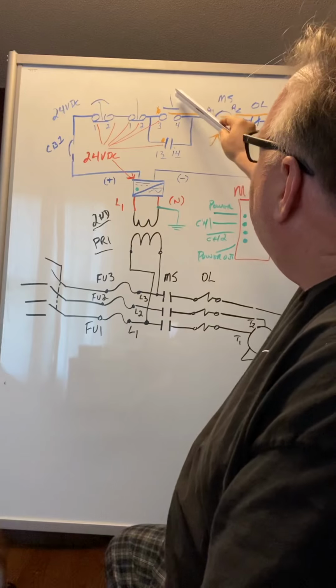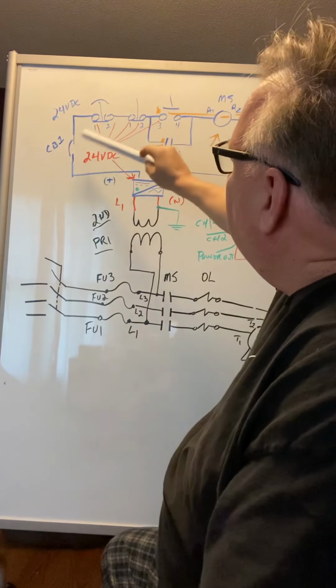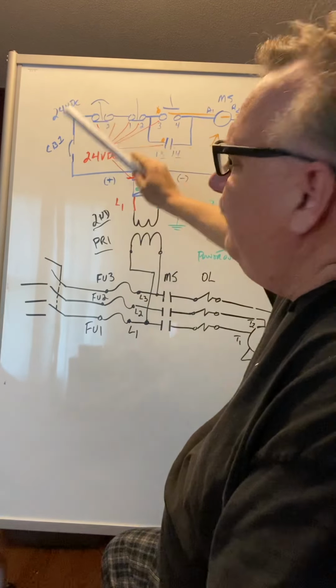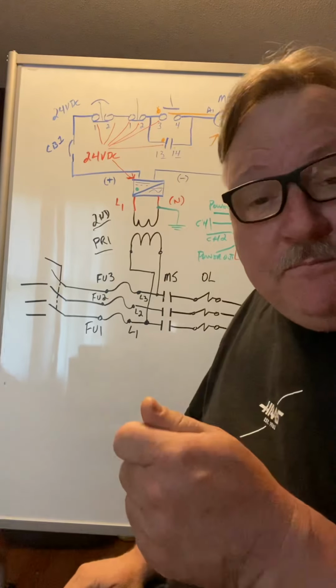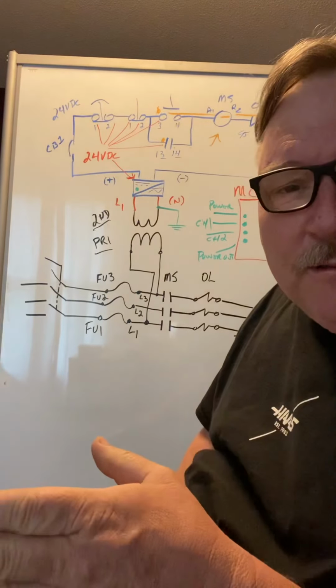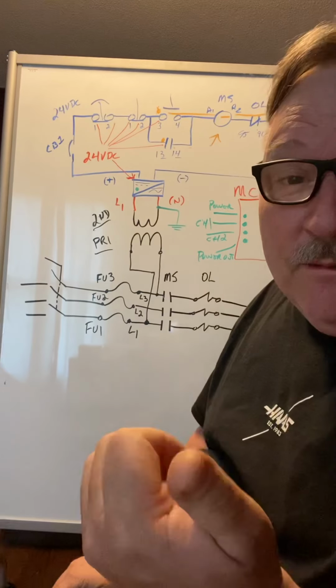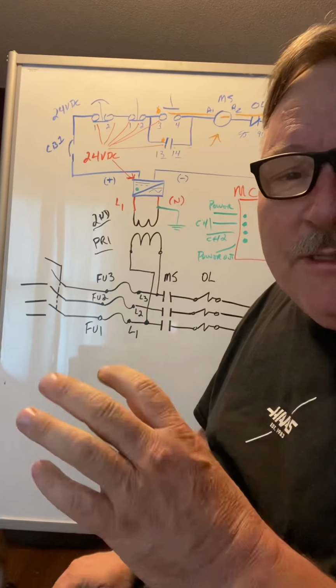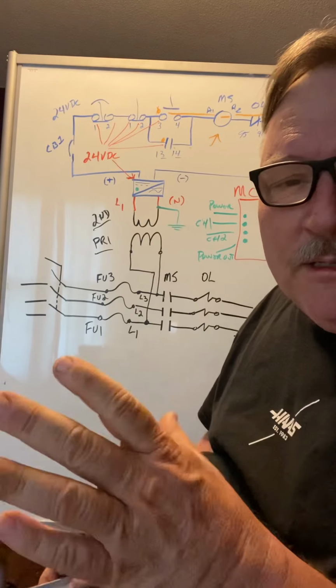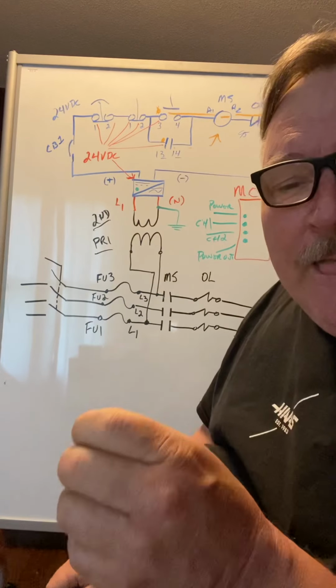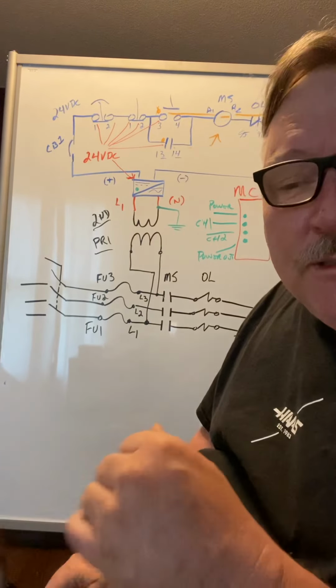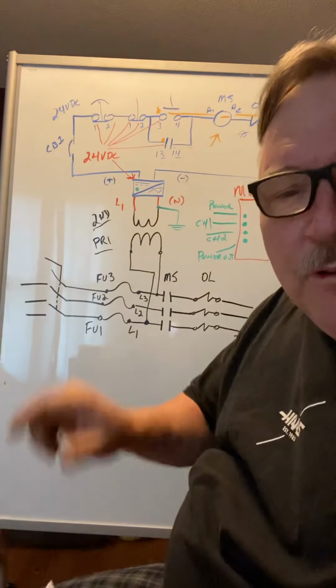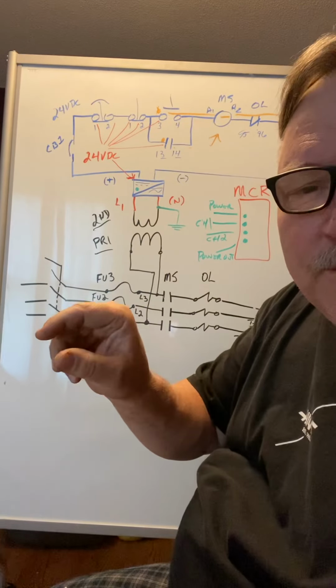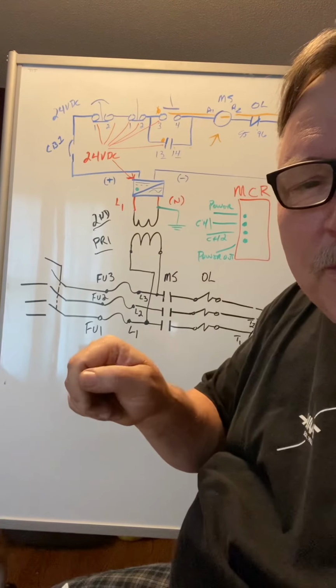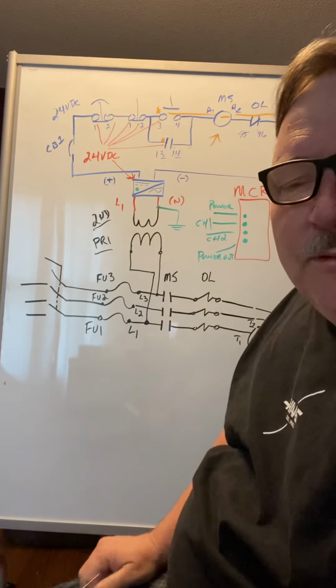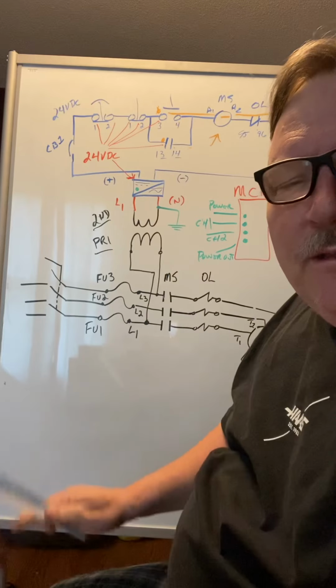So, also, at the beginning, check to make sure that this e-stop has not been pushed in. Operators will forget that they pushed it. Operators' buddies on their way past their buddy's machine will go over there and hit that just to mess with them when they're going on break and things like that. That happens more often than it should. And the guys won't admit it because they didn't press it. So they're like, well, there's nothing wrong with the e-stop. And you go over and go, remember, e-stops take two actions, typically a twisting and a pulling, for that thing to return back to its normal state. So check that. This is before you do anything with your meters.